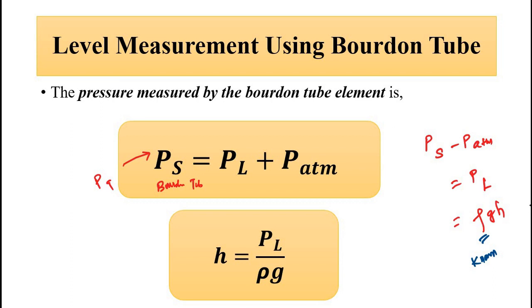Now in case the lid is closed, this atmospheric pressure becomes 0 because it does not get involved in the whole thing. So simply the sensor pressure gives us the liquid column pressure directly. But if it is exposed to the atmosphere, we have to subtract it from the sensor output to get the liquid column pressure.